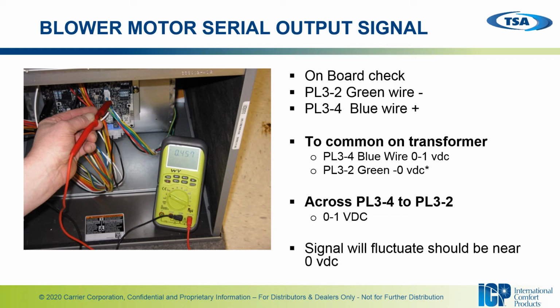And on the blower motor output signal, so this would be what we referenced before as the blower motor feedback or RPM feedback from the motor. You can check between the green wire and the blue wire. Okay, your blue wire is your RPM feedback from the motor to the control board. All right, so between those two, you should see between 0 and 1 volt DC, and it will fluctuate somewhere near 0.